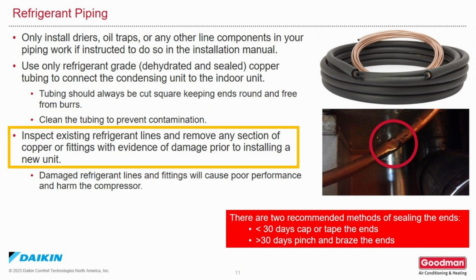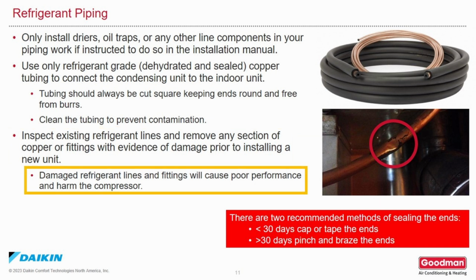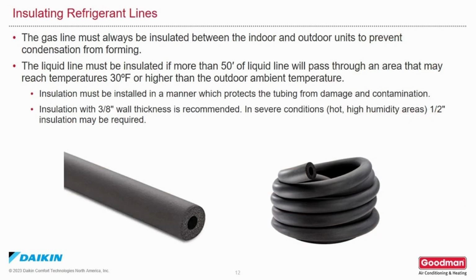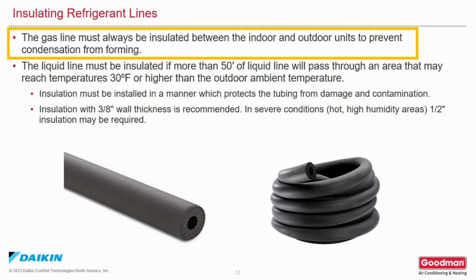If you're reusing an existing line set, inspect it thoroughly. Remove any sections of copper fittings that show damage before installing the new unit. Damaged refrigeration lines and fittings can cause bad performance and damage the compressor. As for insulation on refrigerant lines, the gas line must always be insulated between the indoor and the outdoor unit. This prevents condensation from forming and dripping from the lines.